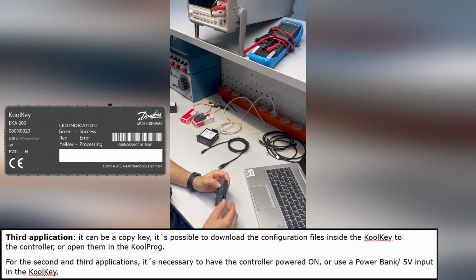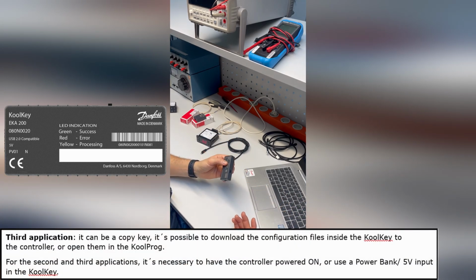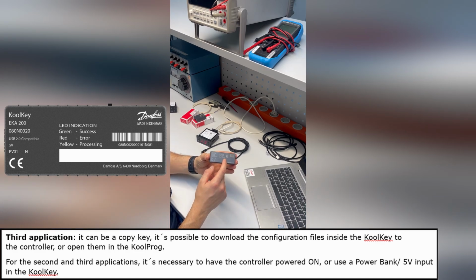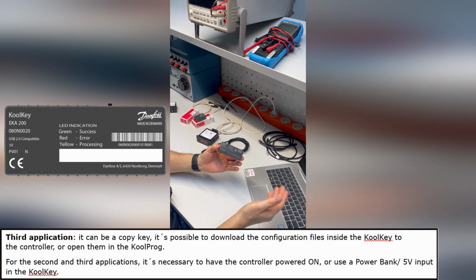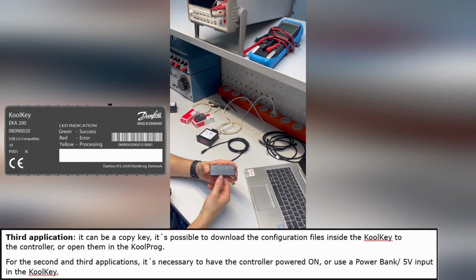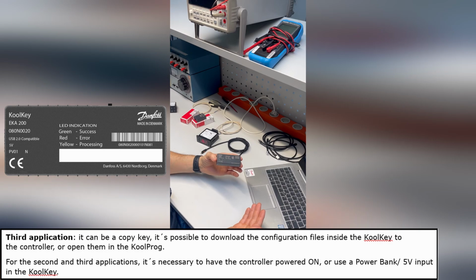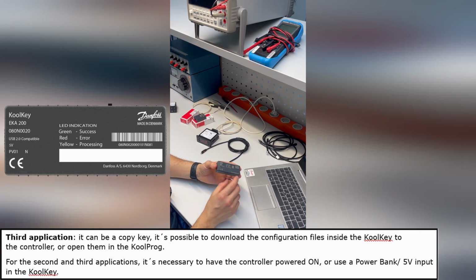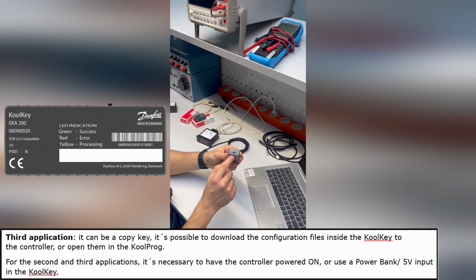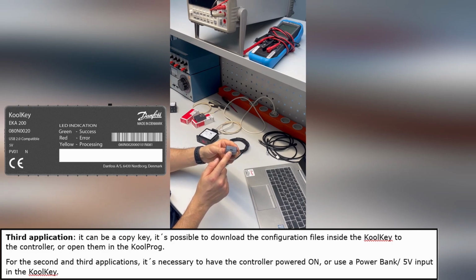The third application is that it can be a copy key. So it's possible to download the configuration files inside the KoolKey to the controller or open them in the Koolprog for edition, for example. For the second and third applications, it's necessary to have the controller powered on or to use a power bank or 5 volts input in the KoolKey. And this is the input of the cable, the USB cable that you connect to your PC, or you can also connect the power bank or 5 volts input over here.